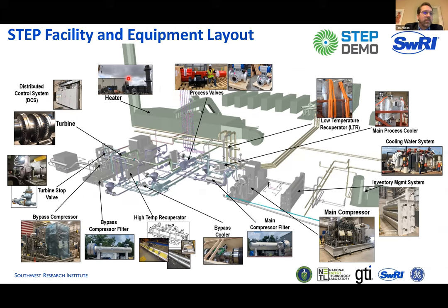But we have a 70 megawatt thermal, which is firing natural gas and providing heat to the cycle. That heat comes through a first-of-a-kind primary process heater using Inconel 740. So hot air blows across the tubes and heats the CO2.